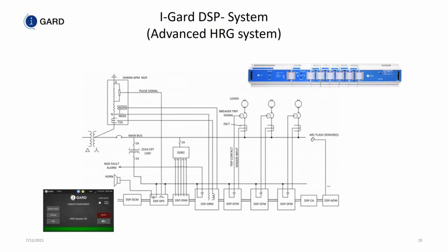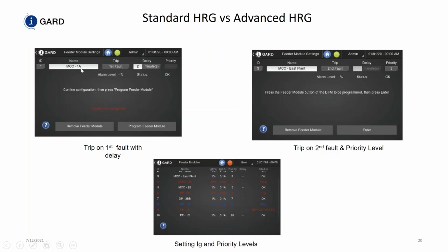So it basically forces your electricians to look for a fault actively, and we give you the tools to look where the fault is. For example, if the fault was in feeder number 1, we tell you the fault is in feeder number 1. You turn on the pulsing and we vary the resistor, creating a signature for you to trace where the fault is. And I guarantee that we can actually find the fault with the iGard system in less than 1 hour in any size facility, because that's how confident we are that this system is effective. We have trending, and you can monitor all the feeders at one glance, and you can detect which feeder has the fault.